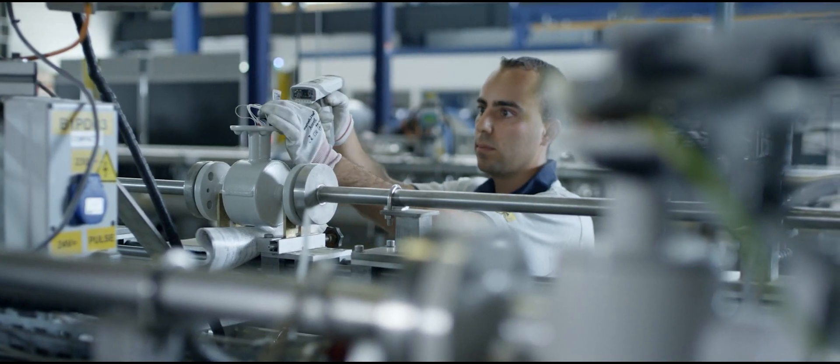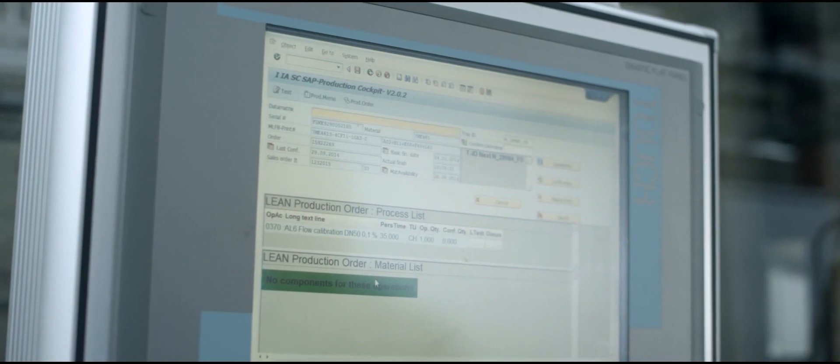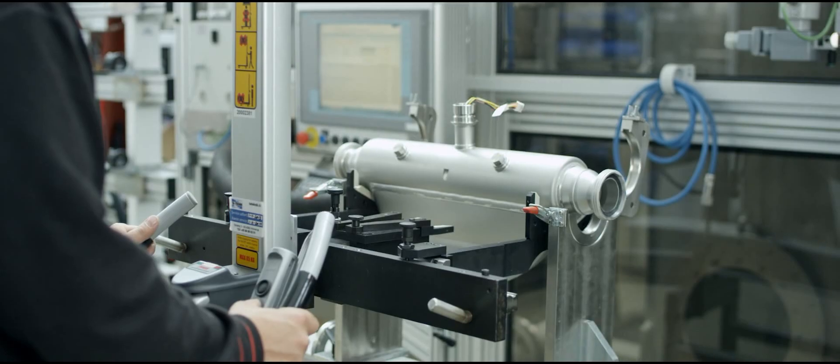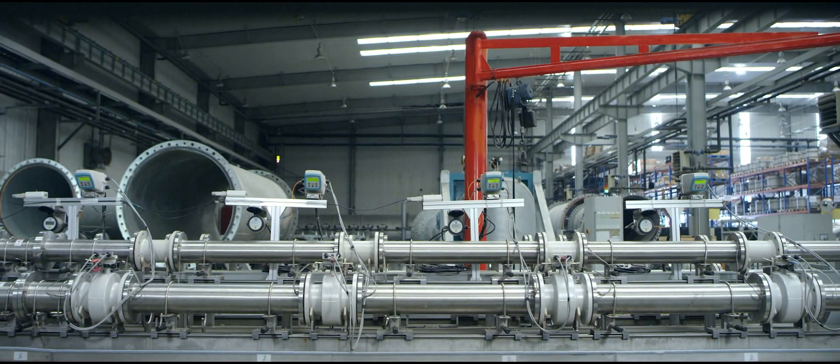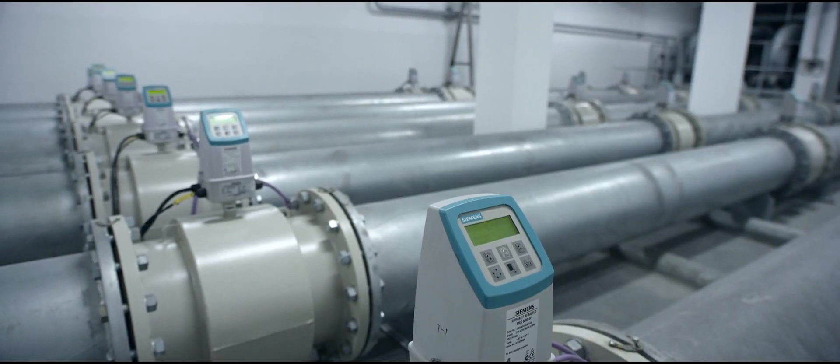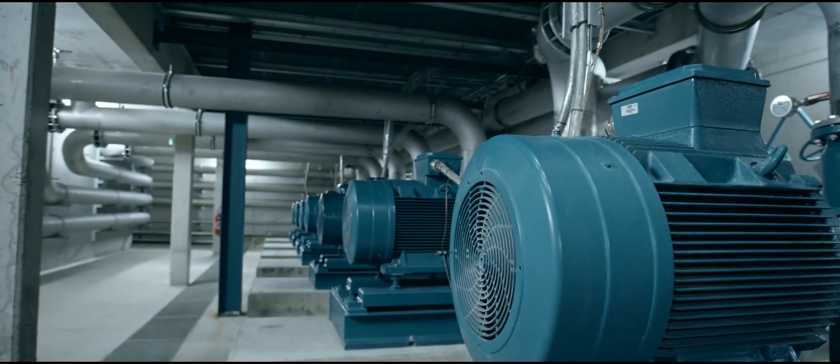You'll get the best possibility for excellent calibration if you use qualified staff with the correct training and years of experience and, of course, accurate equipment. Siemens uses long pipe inlets, more than 10 times the inner diameter of the device. This ensures a fully developed flow profile, giving a stable and constant flow.